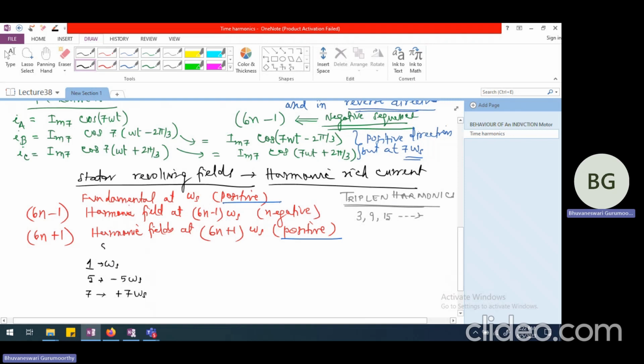These are the stator magnetic fields. Now what happens to the rotor? The rotor will definitely have induced current due to the fundamental, it will have induced current due to fifth harmonic, and it will also have induced current due to seventh harmonic field set up in the air gap.